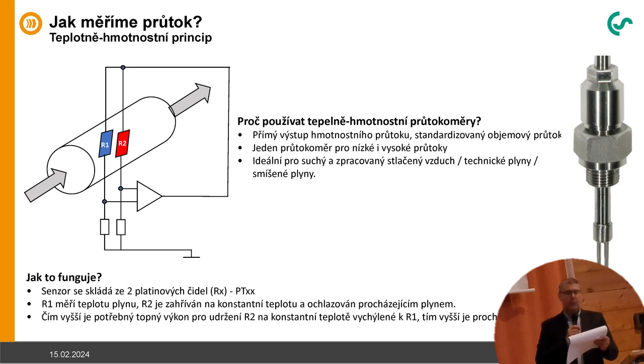There are two resistors, like PT100, like a temperature measurement. The blue one is the cold one, measuring the air temperature, and the red one is heated approximately 8 degrees higher than the blue one. And so the flow will cool down the red one, and the electronics internally increase the heat to keep it at a constant overtemperature. And the more energy the electronics need to feed the PT100 chamber, the higher is the volume flow through your pipe. That's how it works.